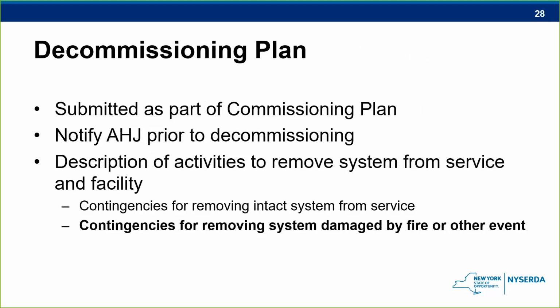Then finally, a decommissioning plan needs to be submitted actually as part of the commissioning plan that we were just talking about. And the authority having jurisdiction must be notified prior to system decommissioning. The plan would include details on providing a safe and orderly shutdown. It includes a narrative of the activities that would be accomplished while removing the system from service, and a listing of any contingencies for removing an intact operational system from service and for removing a system that's been damaged by a fire or other event.